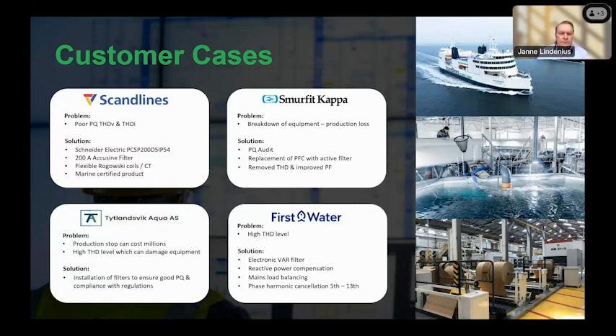Quite fast. Yes, we have made some installations at Scandlines. The class society actually said that Scandlines was not allowed to use the ships. So you can tell me that that's also something called downtime in that case. But they needed to fix the harmonic issues on these boats because they were quite high. We did that by installing some 200 amp filters, 2 on each ship. And they were allowed to sail again. And in the end, I have some contact persons also, so if you need to talk or write an email to these contact persons from Scandlines, they will be happy to answer your questions.